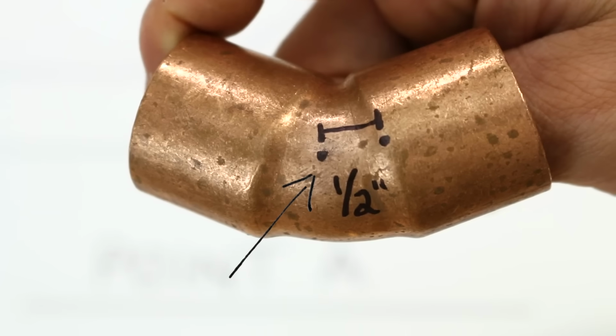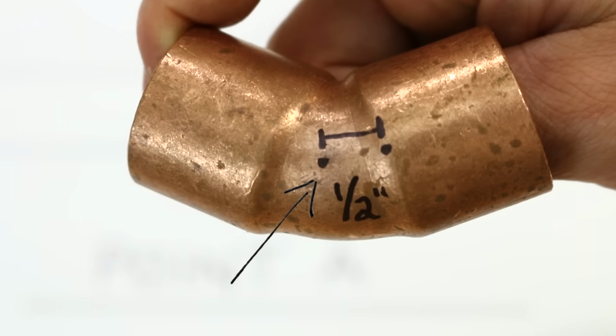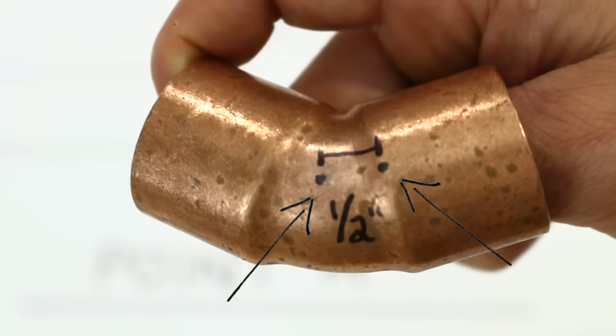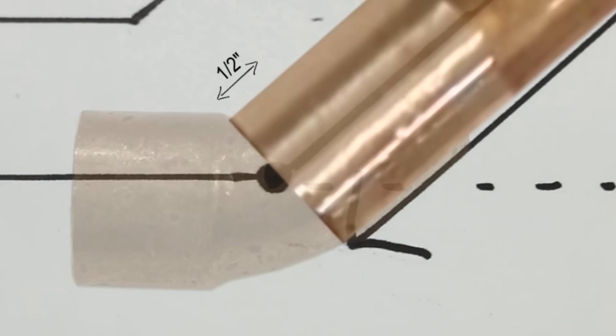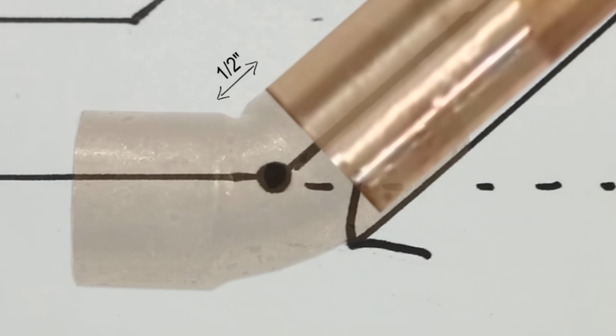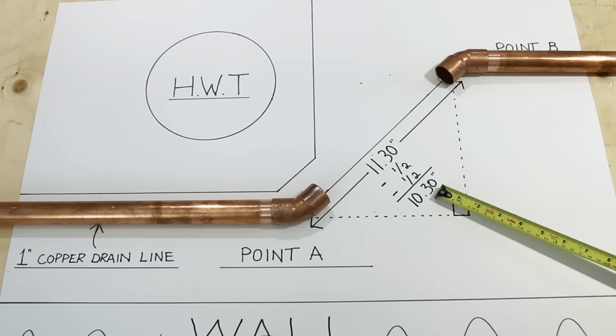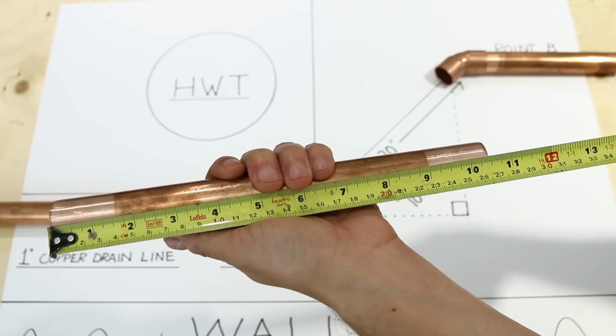So, calculate from the center of the fitting, or the black mark in this case, to the end of the hub portion. This measurement needs to be subtracted 2 times since you have 2 45 degree fittings and you'll be left with your final pipe, which is now the correct length.